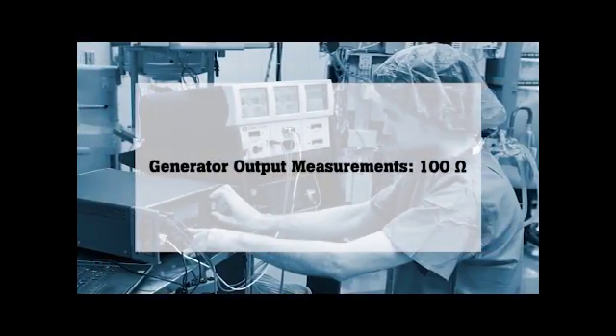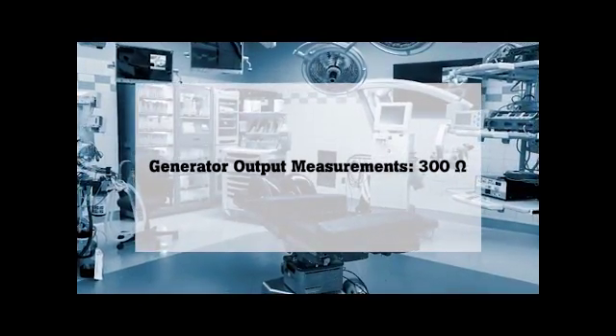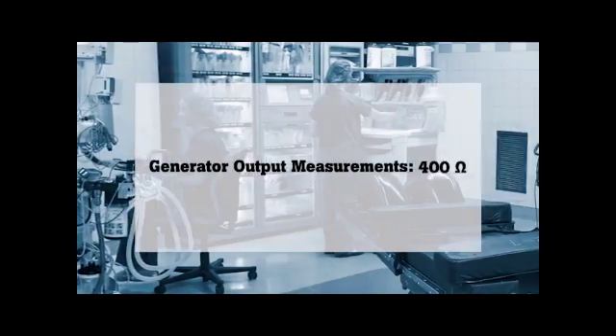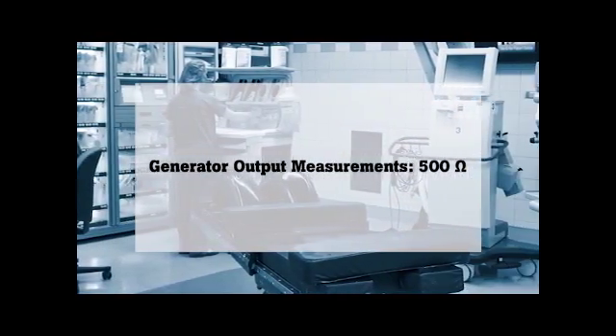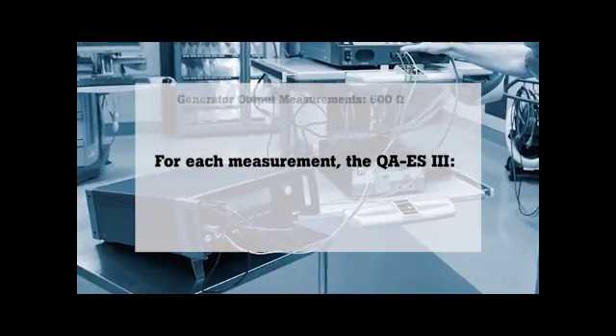The power distribution test makes a series of generator output measurements at different loads from low to high. Measurements begin at the start load resistance and move to the end load resistance at stepped intervals.